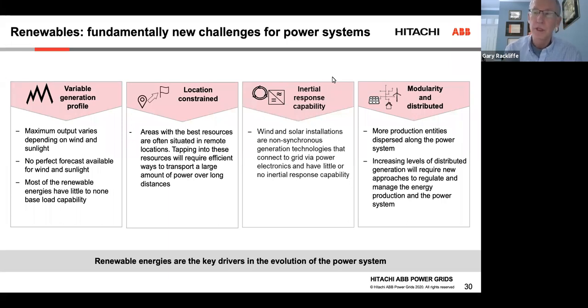What contributes to inertia is the rotating equipment, the rotors basically, of large thermal generation such as coal and nuclear. And when those units start to retire, you can see a drop in the grid inertia, which again is an element of grid stability. Also, there's an issue around short circuit capability that is important. Again, the thermal generation adds to the short circuit capability of the grid, which is important for protection and control. The modularity and distributed aspect is more of a solar PV issue at the grid edge, not as relevant for offshore.